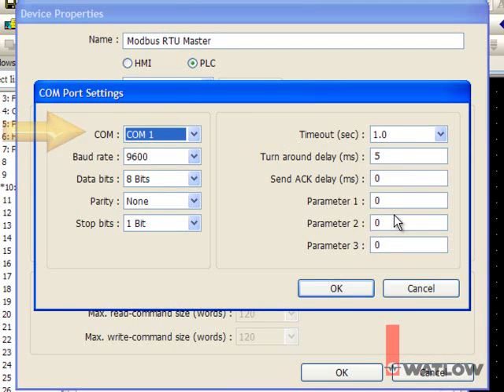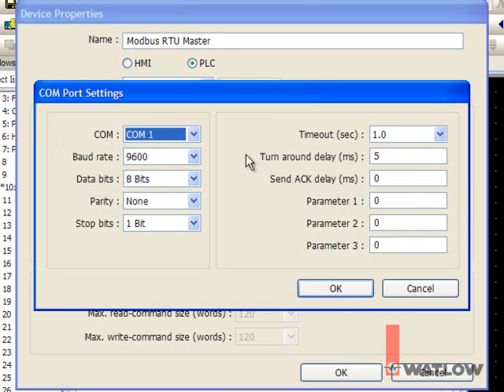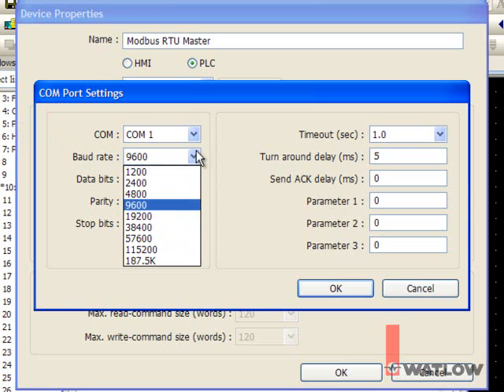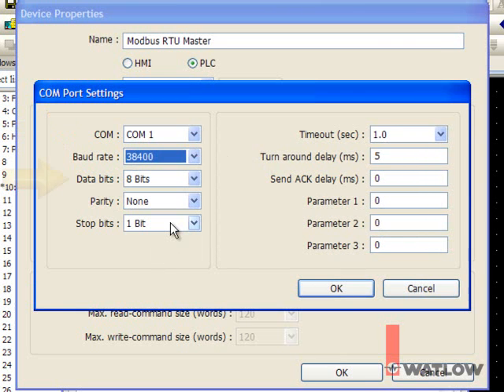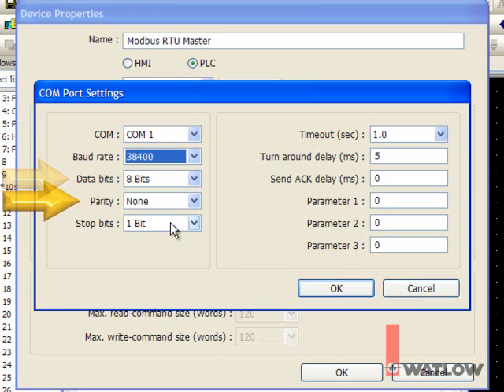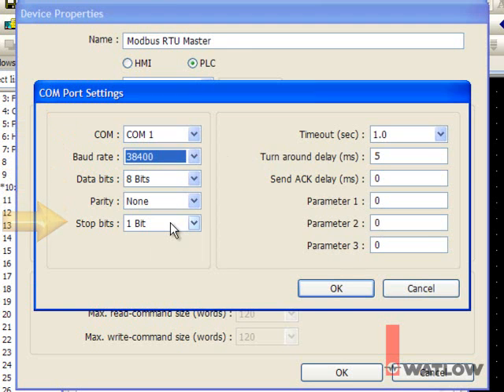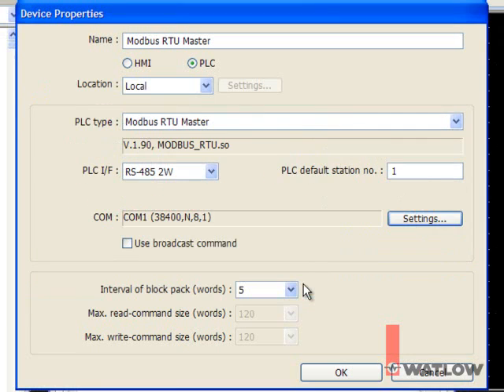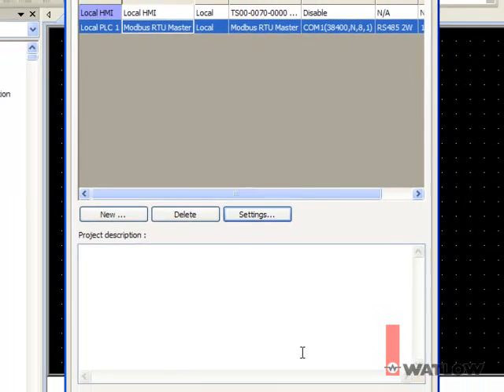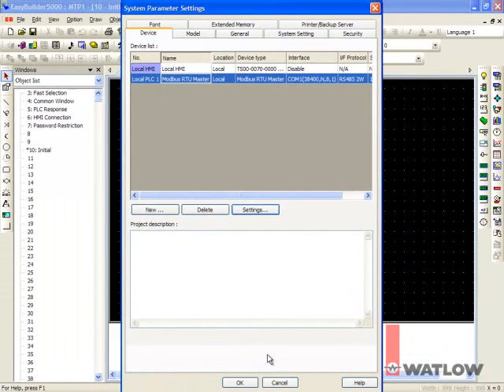We'll use COM 1. Set the BAUD rate. We set the RUI gateway to 38,400, so we must set the same here. Make sure Data Bits is 8, Parity is None, and Stop Bits is 1. Click OK, OK, and OK again.